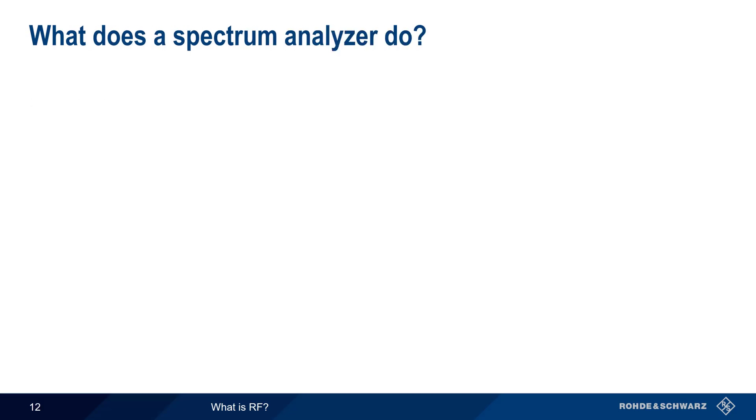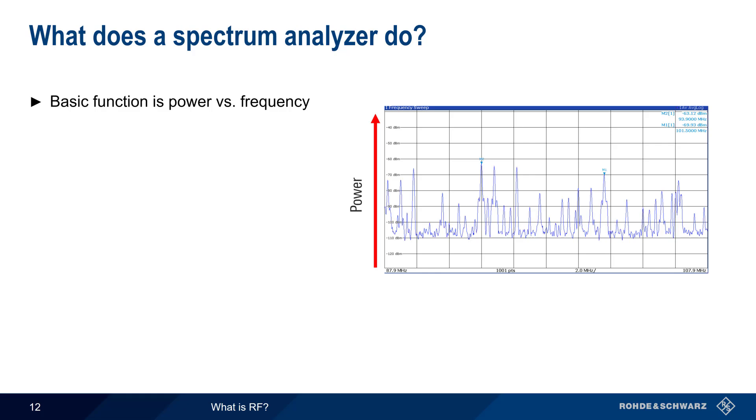The most basic function of a spectrum analyzer is displaying power versus frequency. This is a fancy way of saying that we want to know where RF is present and how much RF is present. In many cases, power is measured relative to other powers and is therefore expressed in dB or decibels.